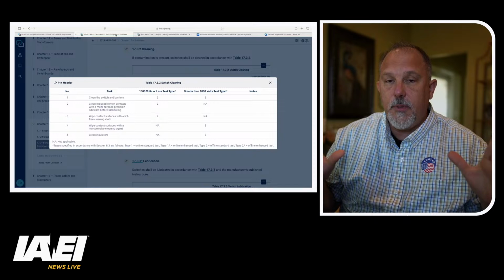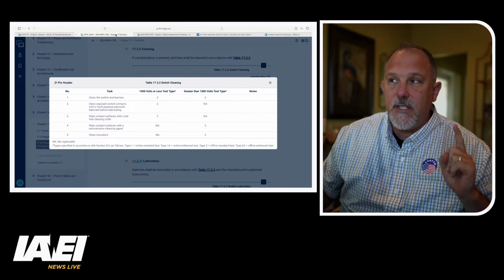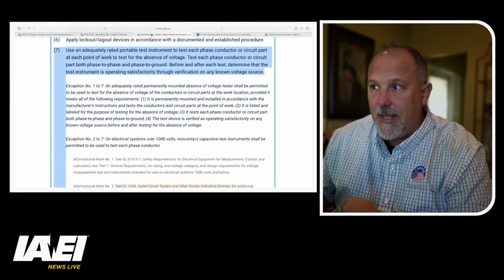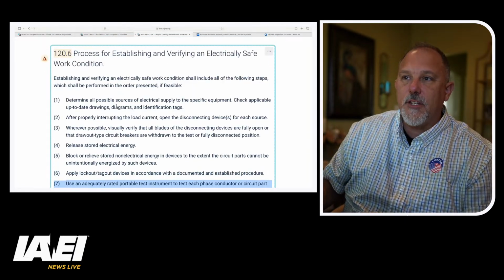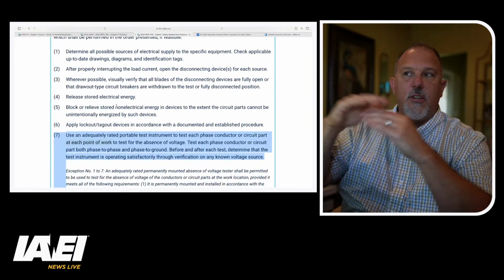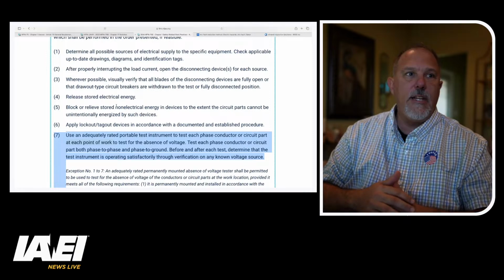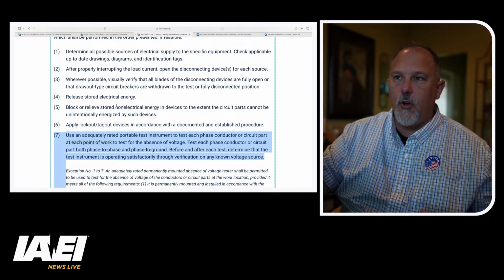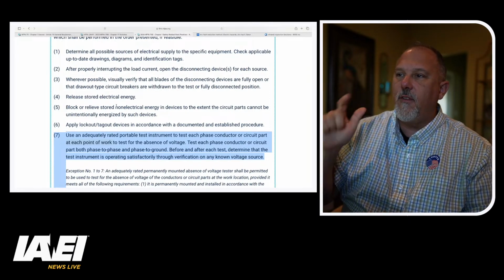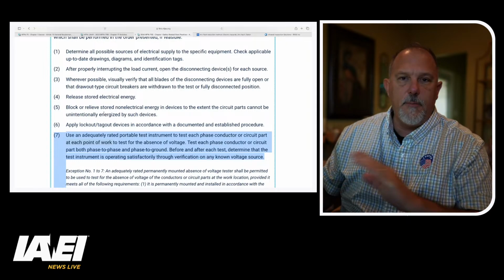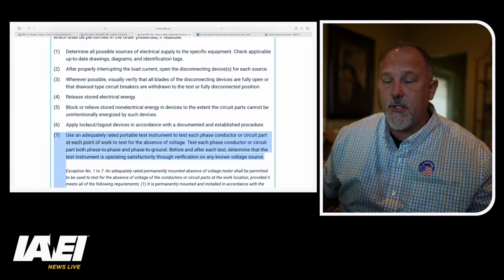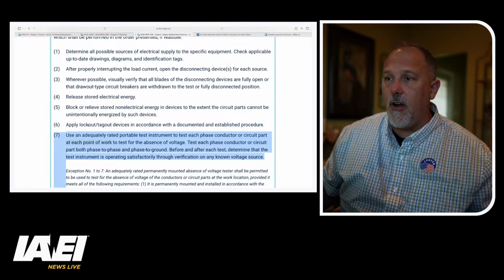And I need to establish an electrically safe work condition. I go to 70E and it tells me to establish an electrically safe work condition, I need to determine all the possible sources. I need to interrupt the load currents, meaning I'm going to open up that switch. Wherever possible, I need to visually verify any of the blades. If it's a molded case circuit breaker upstream, I'm just going to turn the breaker off.